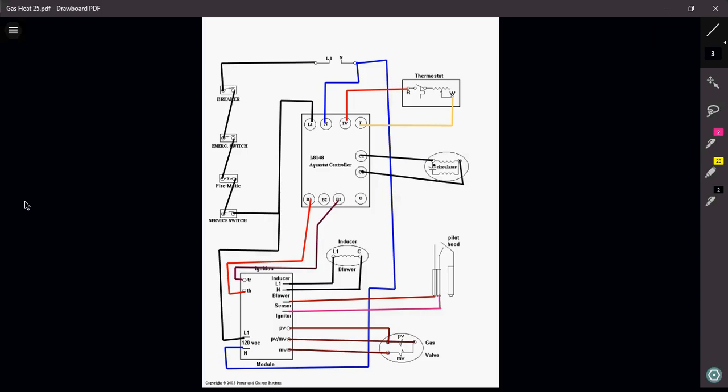Sequence of operation: obviously all of my safeties have to be closed—my breaker, my emergency switch, firematic switch, and my service switch at the actual boiler itself—all have to be closed in order for me to receive power to my aquastat. Once the thermostat calls for heat, I am now going to send that signal down to my ignition module to my TR and TH, which will now send the signal out to my inducer motor.